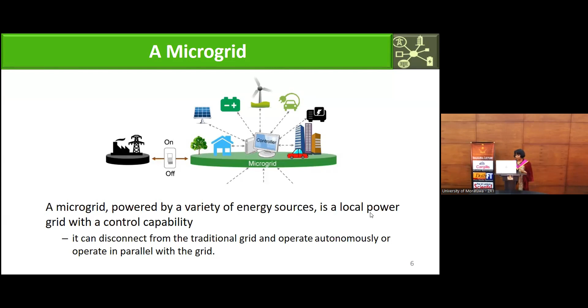Now, since it can operate connected to the grid and as a power island, you should understand that the control must be changed. When it is operating connected to the grid, the frequency is controlled by the grid. But when it is islanded, there should be a grid forming unit, a source, to control the frequency and voltage. So with that understanding, let me go further.